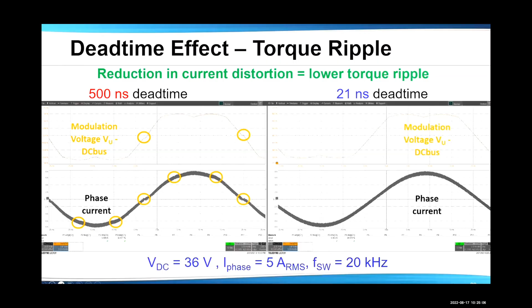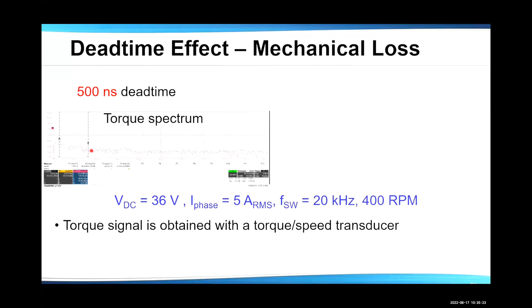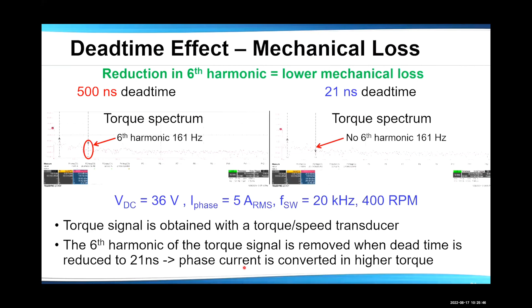And what is then the effect? We measure the torque spectrum with a real torque transducer. And here we get a harmonic, which is there because of the dead time. This harmonic is not there if you reduce the dead time. If the current is the same, flowing into the same motor, then the energy of this harmonic goes into the DC component of the torque. So at the end of the day, the net result is that on the same phase current, you get higher torque from the motor. And this is going to play an important role in efficiency.